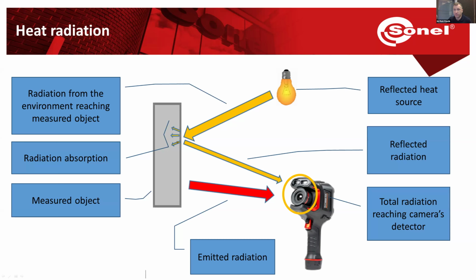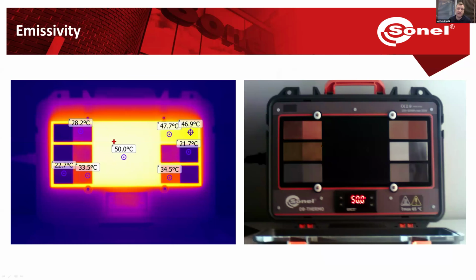Once they are pointed at the object, some of this radiation will get absorbed and some will get reflected and reach the detector of our camera. So how do we correctly get this value, both reflected and emitted radiation reaching our camera, so we would get the temperature reading just from the emitted radiation? Well, for this, we need to set the emissivity.